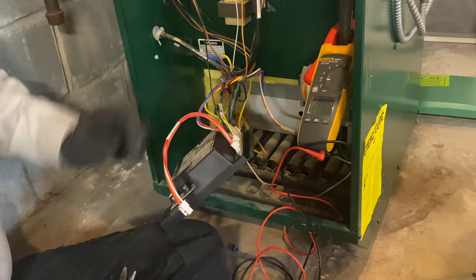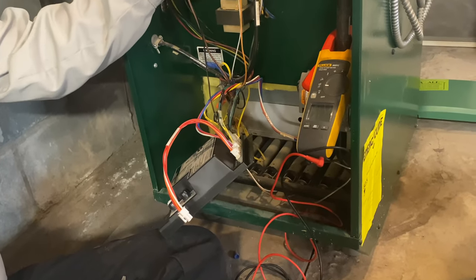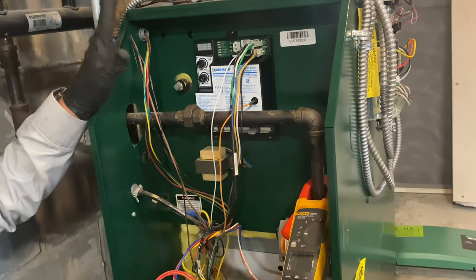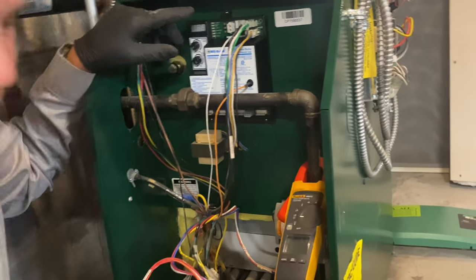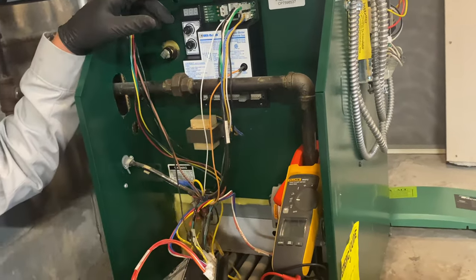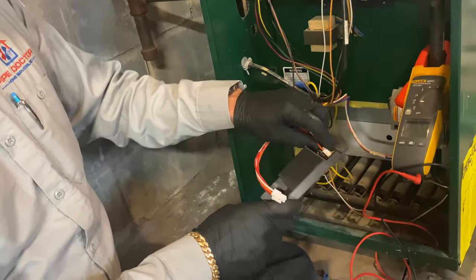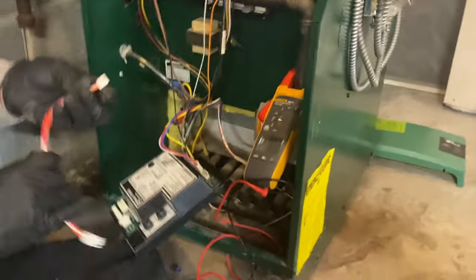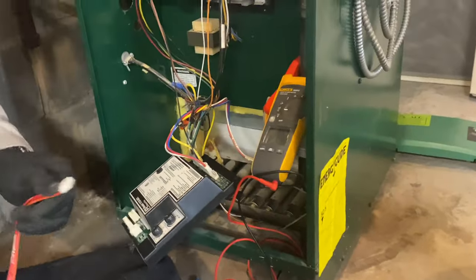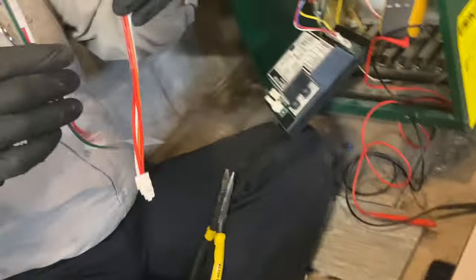The only thing we did not plug back in was that wire right there, because that goes to the circulator. If this was only a one zone boiler, you'd utilize that, which comes with the boiler, and they just didn't bother to remove it. Okay, now this wire is the same as this, right? We'll go over that later. That's the wire going to the temperature and pressure probe.